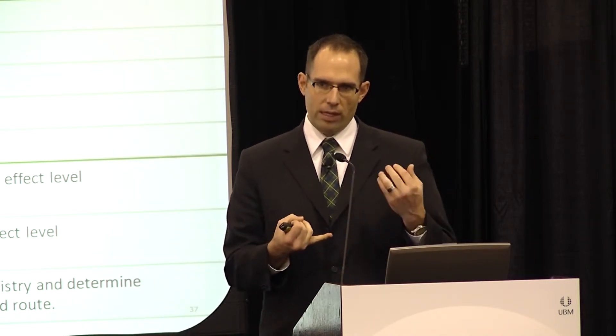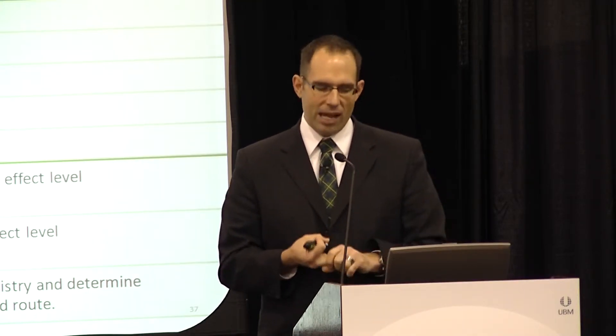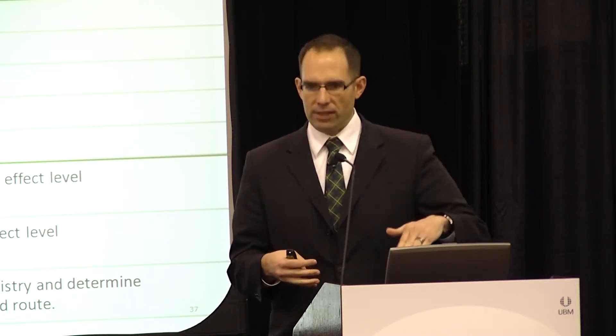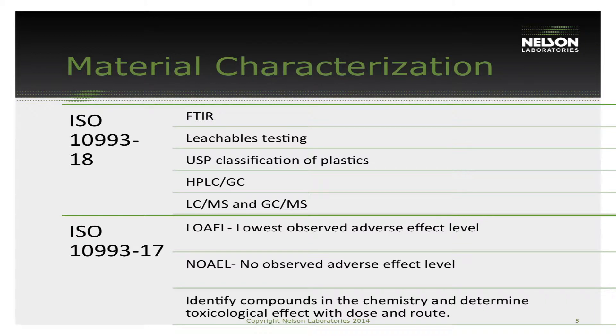Some of the more common chemistry techniques are GCMS, which looks for volatile and semi-volatile compounds, HPLC, and FTIR. These techniques help us identify and quantify what's in that solution. ISO 10993-17 then takes that data and uses it for toxicological output — to identify these compounds and what concern they present to the patient from a toxicological endpoint.